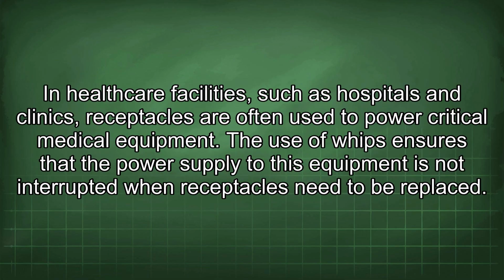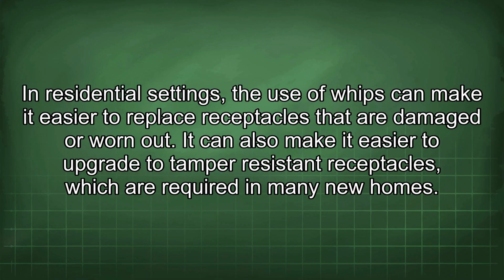In healthcare facilities, such as hospitals and clinics, receptacles are often used to power critical medical equipment. The use of whips ensures that the power supply to this equipment is not interrupted when receptacles need to be replaced. In residential settings, the use of whips can make it easier to replace receptacles that are damaged or worn out. It can also make it easier to upgrade to tamper-resistant receptacles, which are required in many new homes.